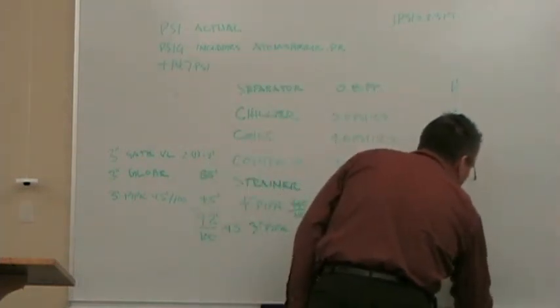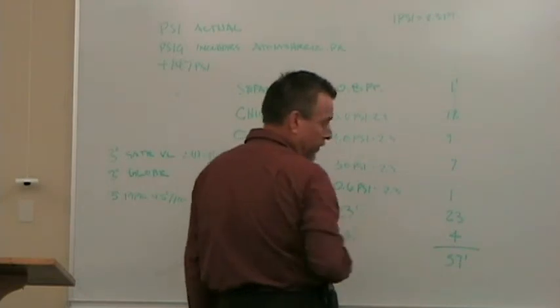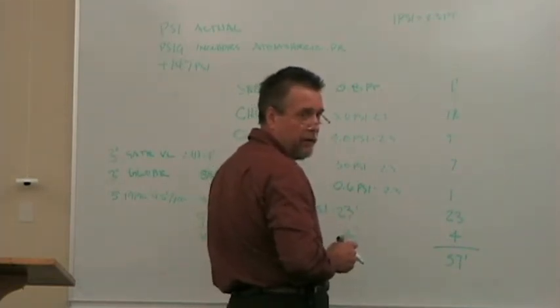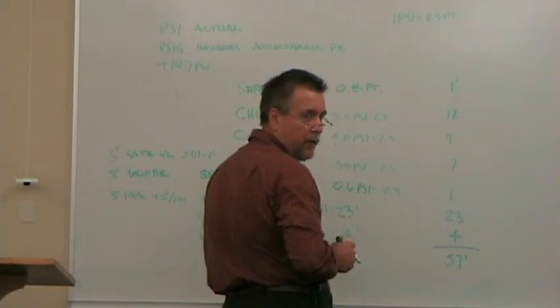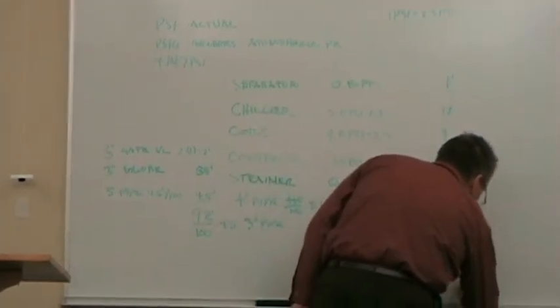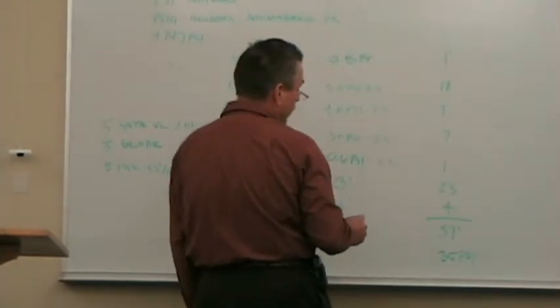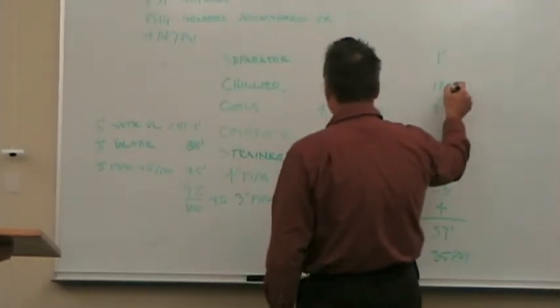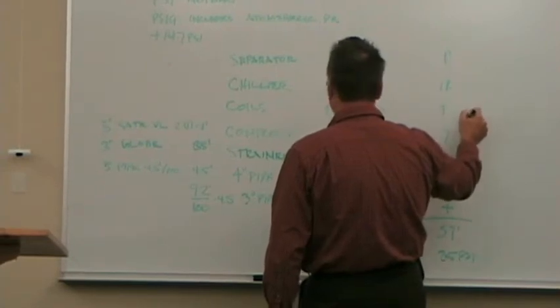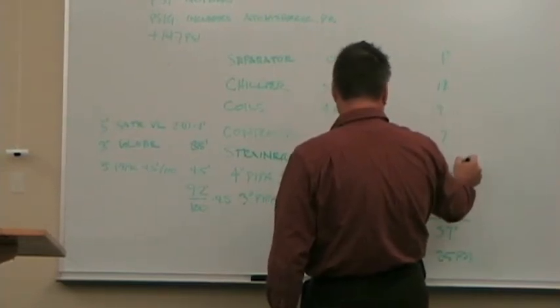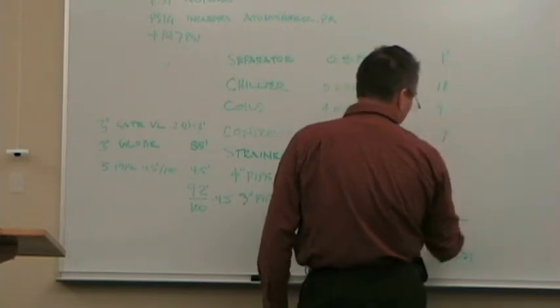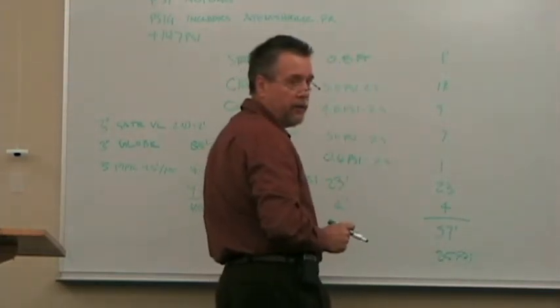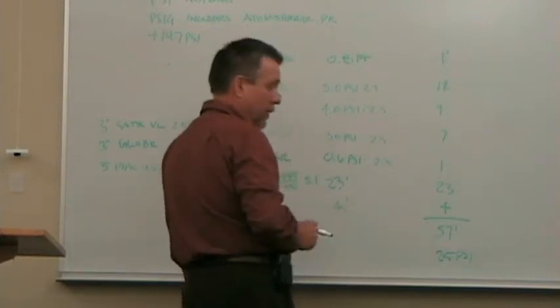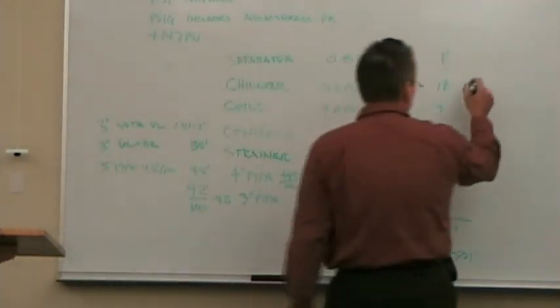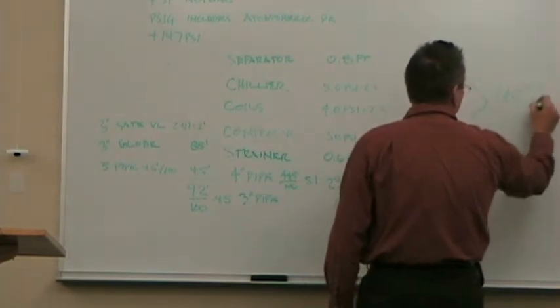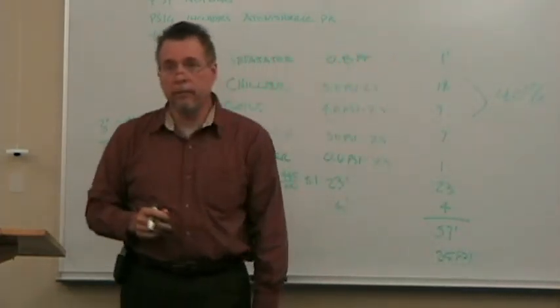57 feet of pressure drop. What's that divided by 2.3? 24.7, or 25 PSI drop in our piping system. So let's just look at the chiller and the coils and the strainer. The strainer wasn't very much, but 21, what's 21 divided by 57? 0.368. 40% of my pressure drop.